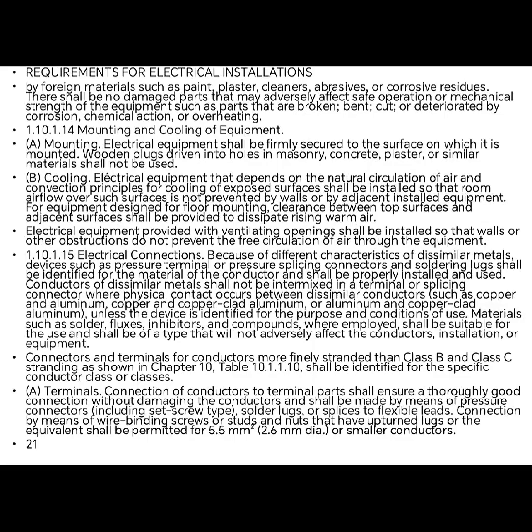Electrical connections. Because of the different characteristics of dissimilar metals, devices such as pressure terminals or pressure splicing connectors and soldering lugs shall be identified for the material of the conductor and shall be properly installed and used. Conductors of dissimilar metals shall not be intermixed in a terminal or splicing connector where physical contact occurs between dissimilar conductors, such as copper and aluminum, copper and copper-clad aluminum, or aluminum and copper-clad aluminum, unless the device is identified for the purpose and conditions of use.